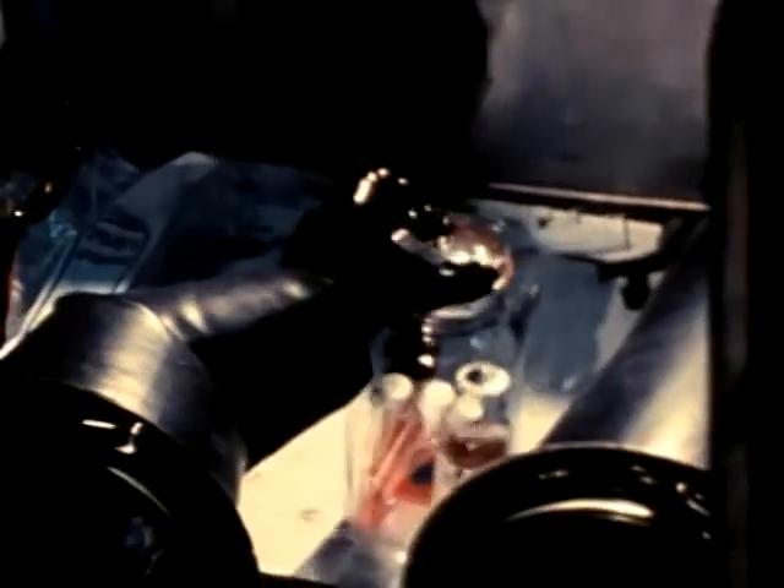Note how the attached gloves are pulled back inside the cabinet. This is due to the negative air pressure that is constantly maintained within the cabinets. This added safety feature ensures that no organism escapes should the gloves be punctured.